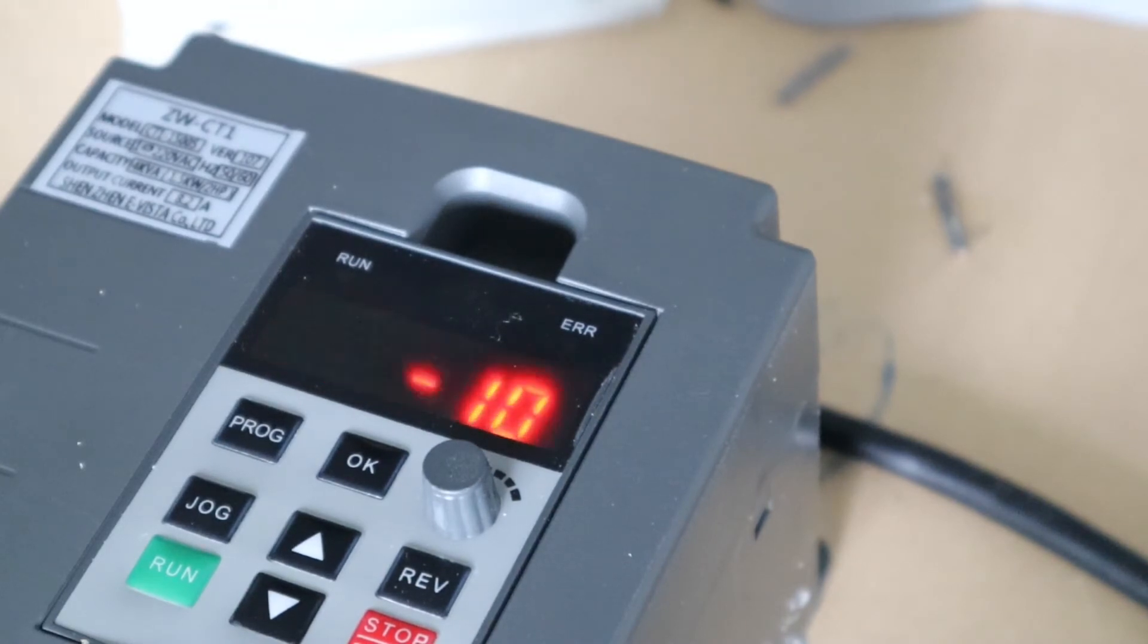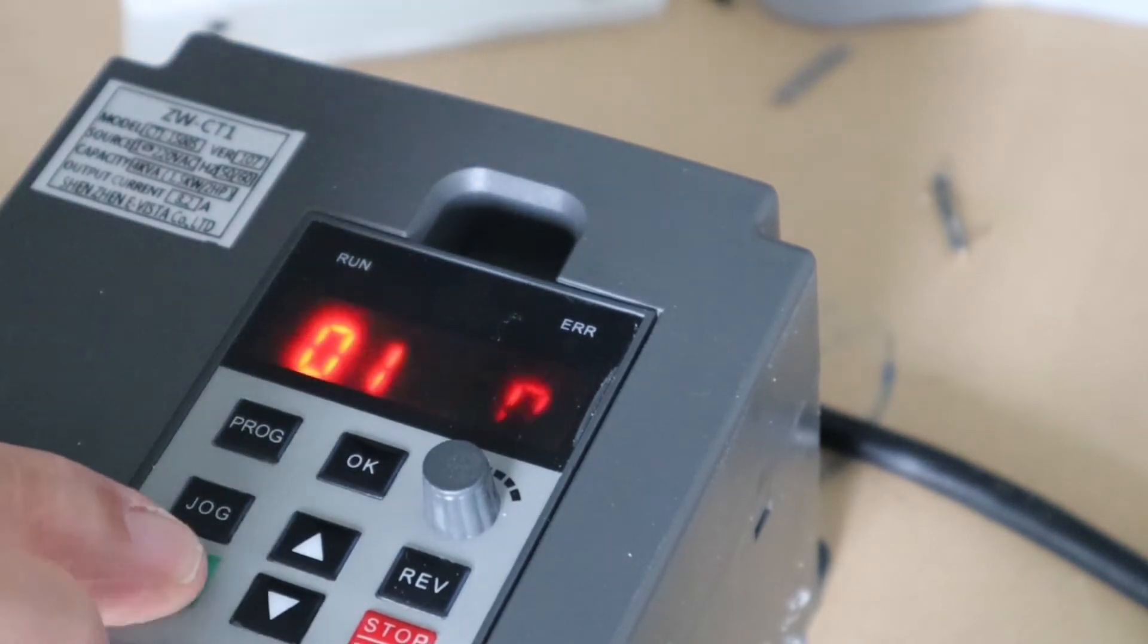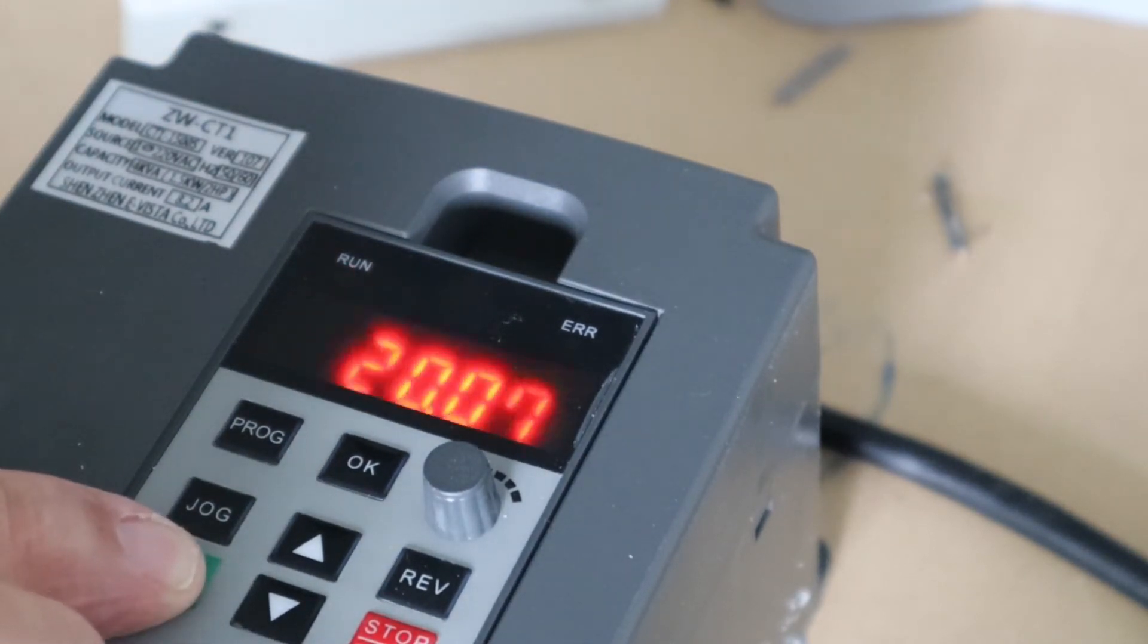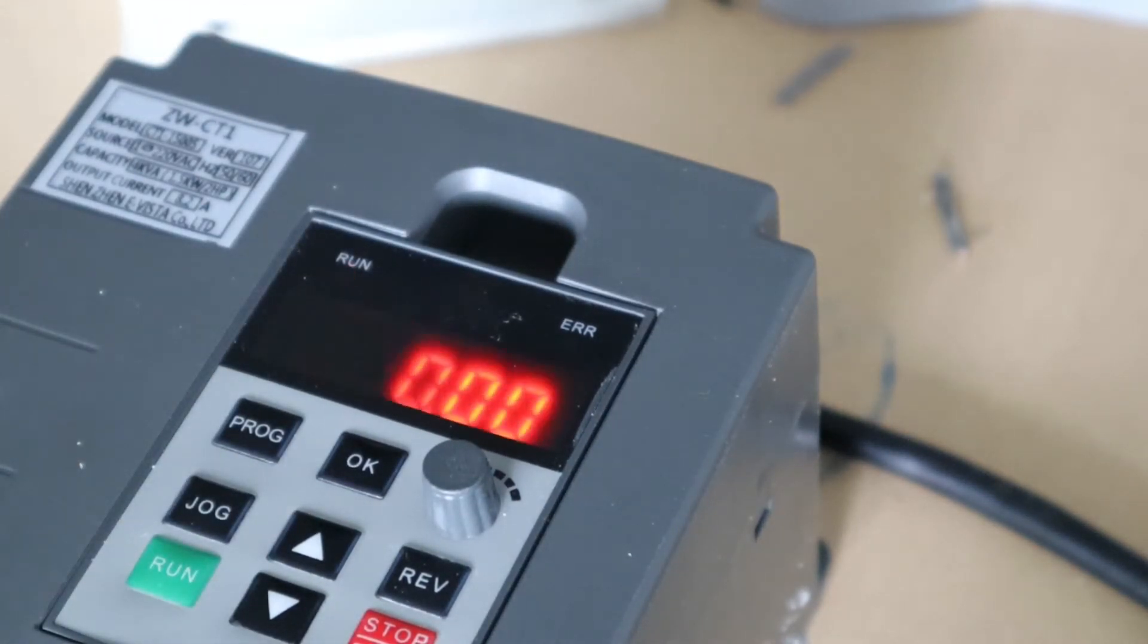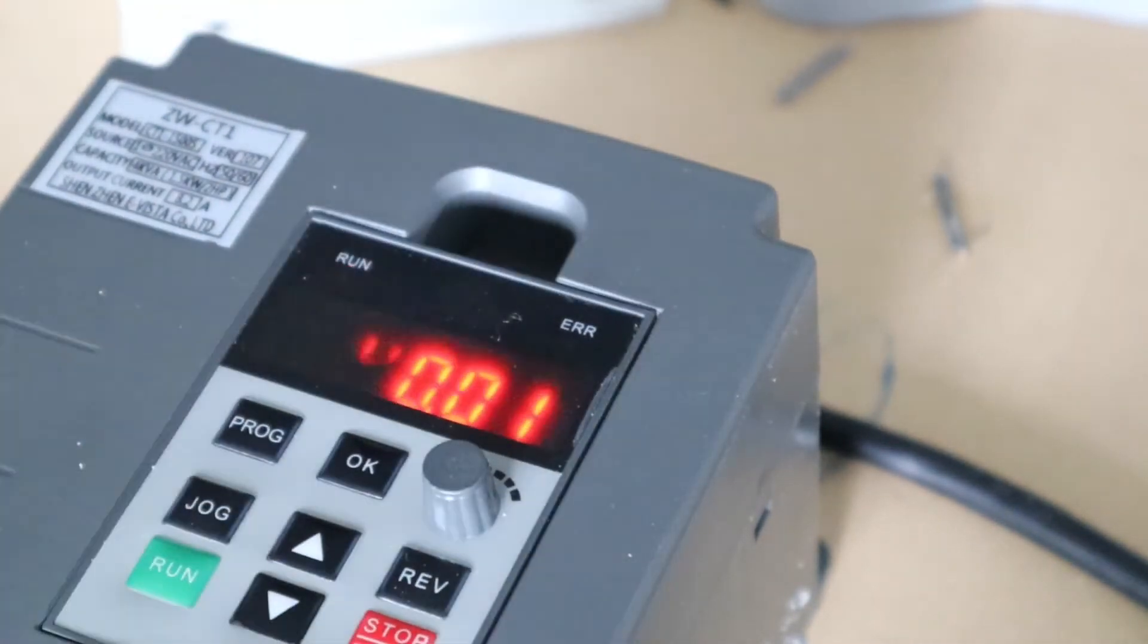Now that is the speed. So what we should be able to do now is switch it on and it should go straight up to 50 hertz in 2 seconds. That is what it is done. It will take it off and it should close down in 2 seconds. So that is what we have got now. We have got it moving up the scale for 2 seconds and down again closing off.